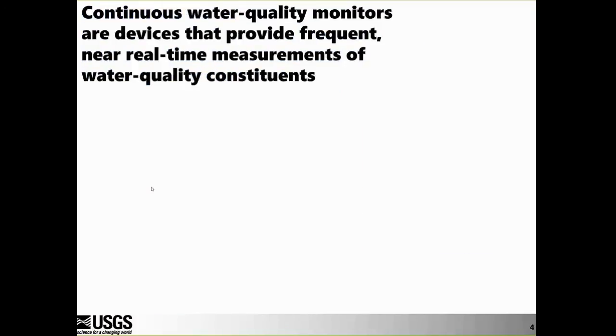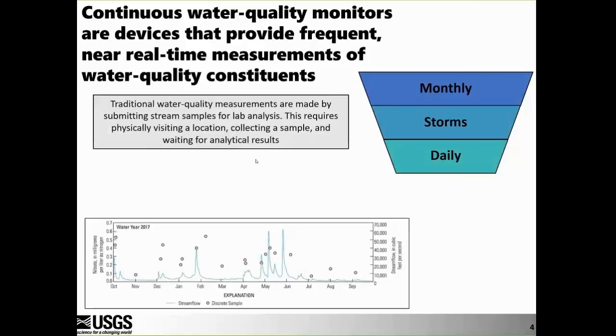Continuous water quality monitors are devices that provide frequent, near real-time measurements of water quality constituents. This contrasts with traditional water quality measurements, which require someone to physically visit a location, collect a water sample, bring it back, process it, submit it to a lab, and wait for results — which can be done monthly, targeting storms, or on a daily basis.